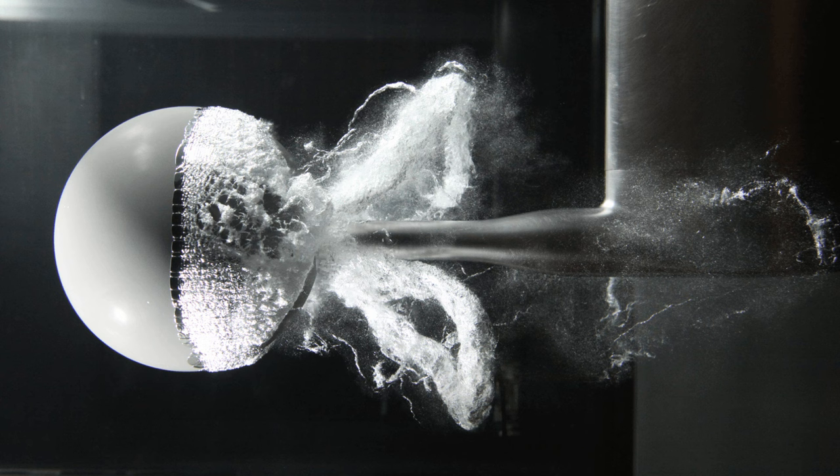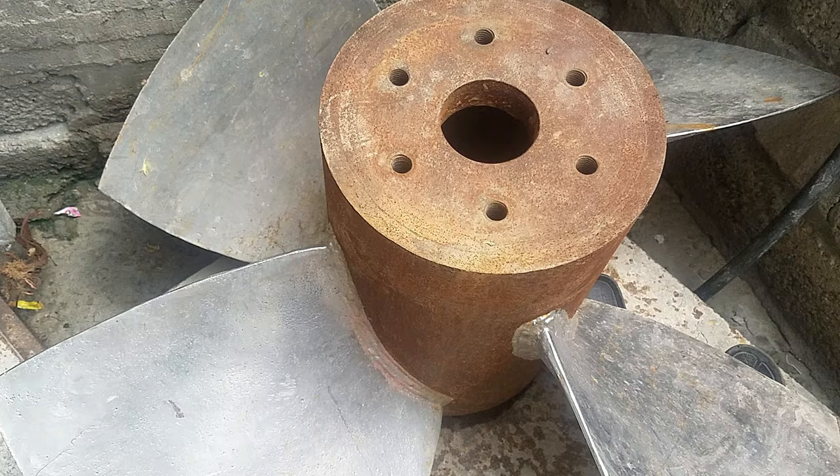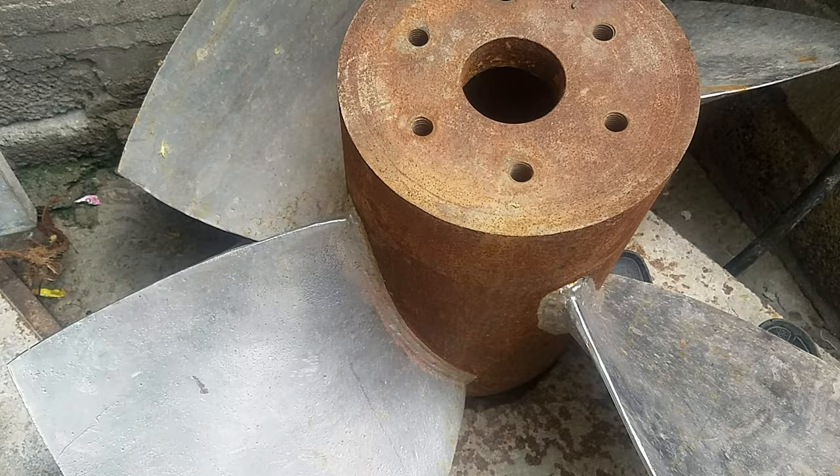Collapsing voids that implode near a metal surface cause cyclic stress through repeated implosion. This results in surface fatigue of the metal, causing a type of wear also called cavitation. The most common examples of this kind of wear are pump impellers, turbine blades, and bends, where a sudden change in the direction of liquid occurs.